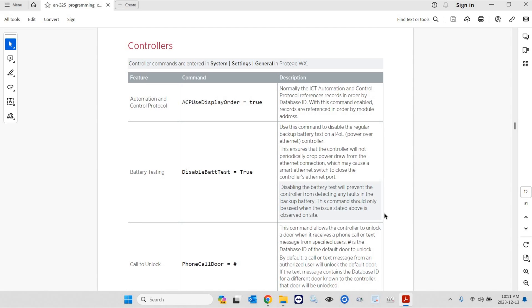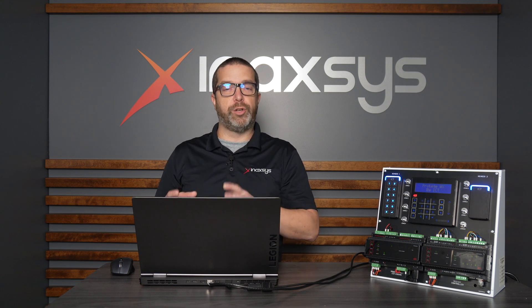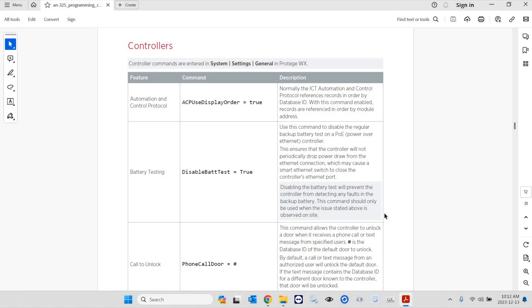Commands that we use a lot on WX or GX systems, especially when you have upgraded to the latest firmware, or if you're switching from a Protege SE system to a GX or WX and you have some Ethernet modules like the PRT-RDE2 PCB, or if you have PRT-MNR2s — the repeater module from ICT. By default, the UDP and TCP ports are closed in the latest firmware version. So if you pick a brand new GX or WX controller from the shelf, by default you cannot ping the device because it's protected, and you cannot connect the MNR2 or ICT entry station intercoms because the port is closed.